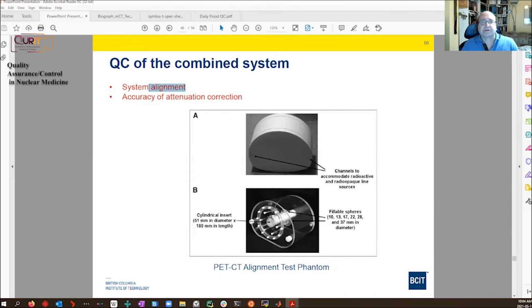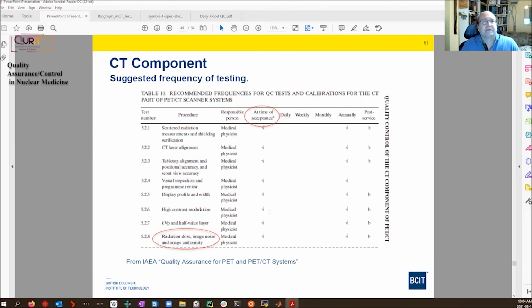For the combined system, the main thing is we want to get system alignment so that when we use the CT for attenuation correction, the attenuation image or the attenuation map aligns with the reconstructed emission image. And so we have various phantoms that have parts that are detected by CT and parts that are detected by PET or SPECT. And so this type of alignment needs to be done. So again, I just give you these for your interest.